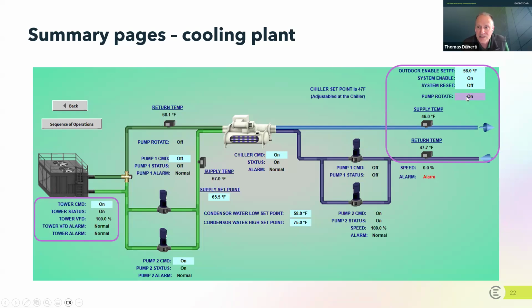But what this does is it tries to keep both pumps running for roughly the same amount of time. And saying that a different way, this pump might run for 24 hours and then this pump run for the next 24 hours. And they'll alternate back and forth because strategically, what you want to do is get equal wear and tear in these pumps because it's cheaper when you replace one pump to replace both pumps at the same time, get the contractor out there one time to do it. And so what you want to do is you want to have equal wear and tear. And so you see this in the system as well, where you want to rotate or make sure that the life cycle of these, they run in parallel.